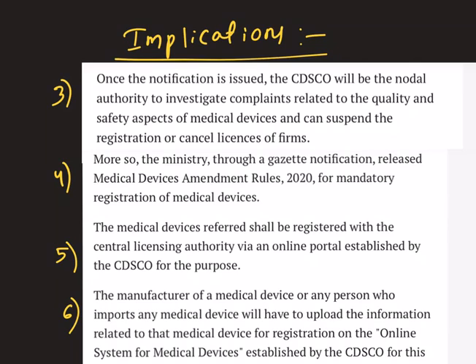More importantly, the medical devices referred to shall be registered with the Central Licensing Authority via an online portal established by the CDSCO for this purpose. Besides, the manufacturer of a medical device or any person who imports a medical device will have to compulsorily upload information related to that device for registration on the online system.